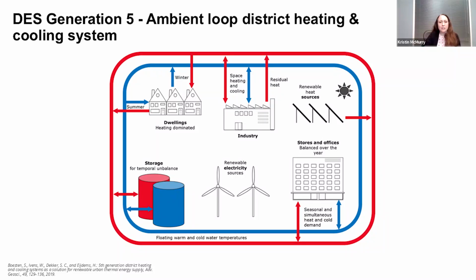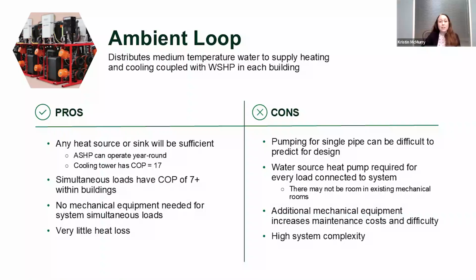If you go to the next slide, we'll talk about the pros and cons. The high system complexity is one of the biggest things. The water source heat pumps are a different size for each building, so you can't just swap one in for another, there's so much more mechanical equipment. If we're looking at an existing system compared with a brand new system, it's a pretty good fit for something brand new, but we're usually dealing with existing systems, and whether mechanical rooms actually have space for that much equipment is a big question.